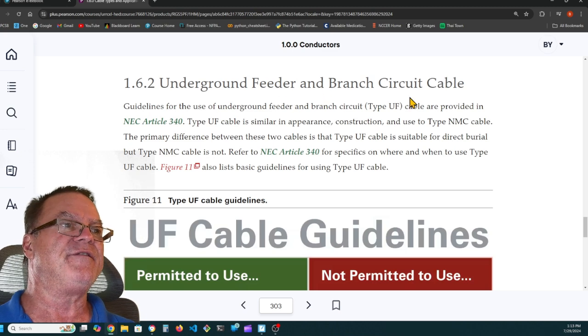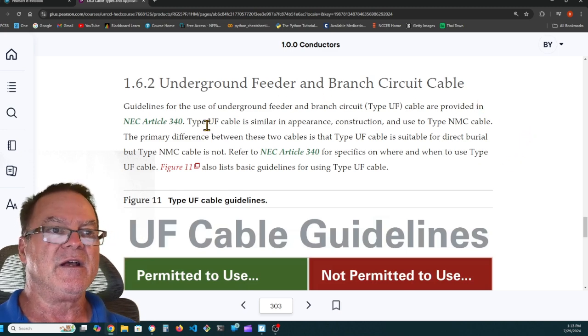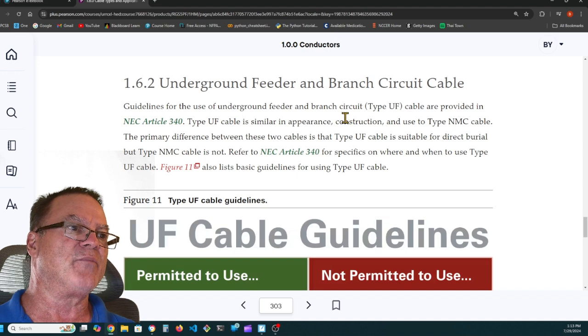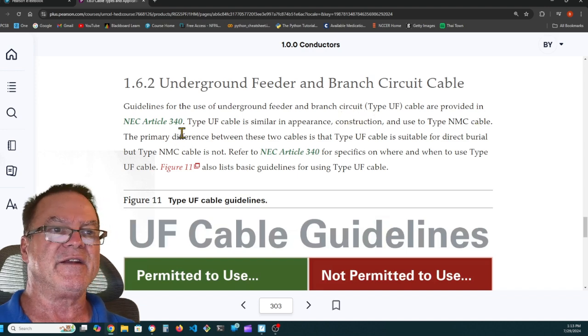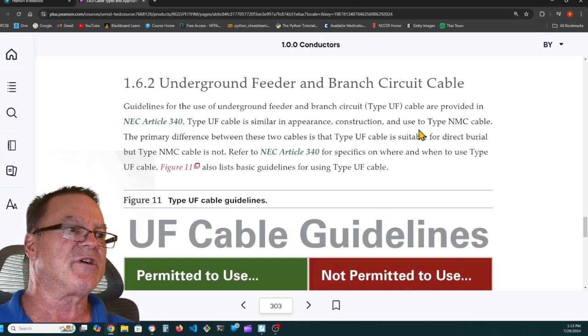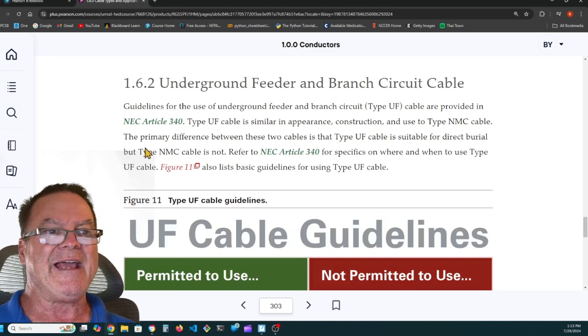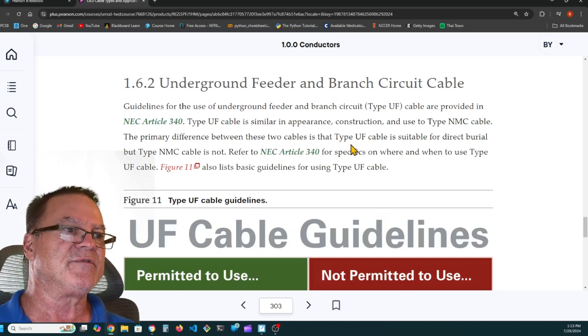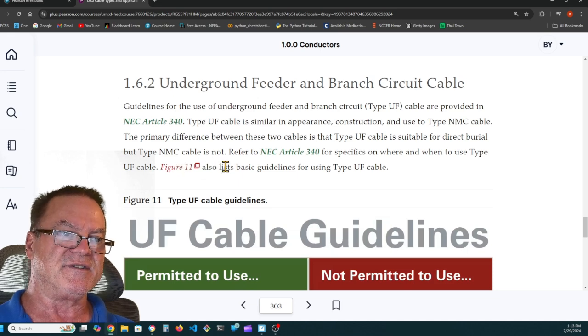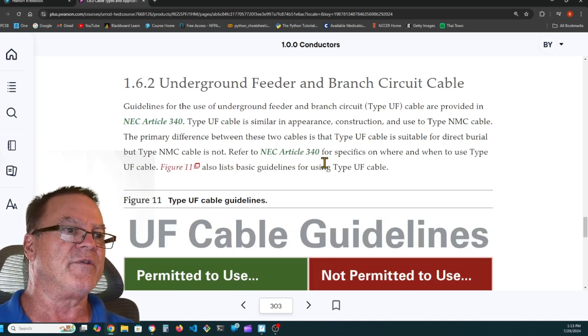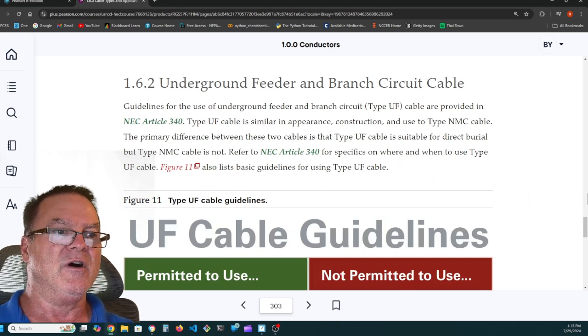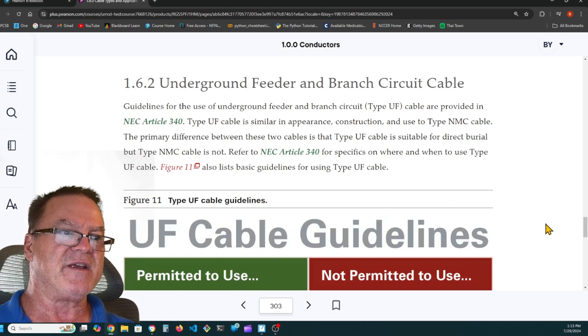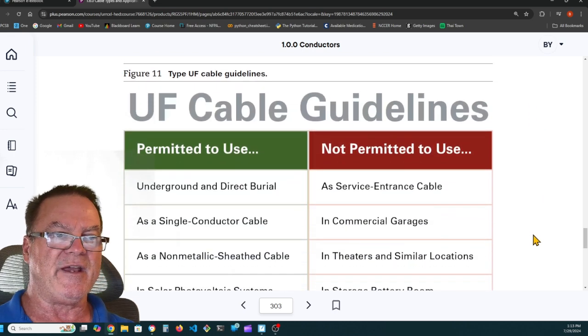1.6.2 Underground feeder and branch circuit cables. Guidelines for the use of underground feeder and branch circuit cable are provided in NEC Article 340. Type UF cable is similar in appearance, construction, and use to type NMC cable. The primary difference between these two cables is that type UF cable is suitable for direct burial, but type NMC is not. Refer to Article 340 for specifics on where and when to use type UF cable. Figure 11 also lists basic guidelines for using type UF cable.